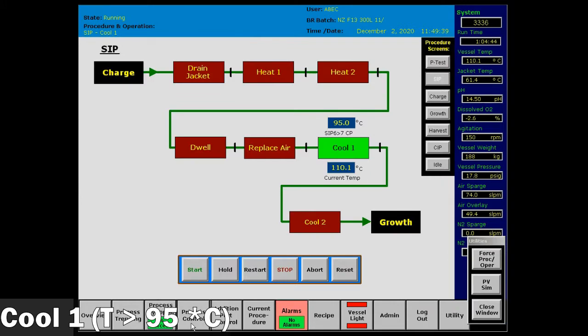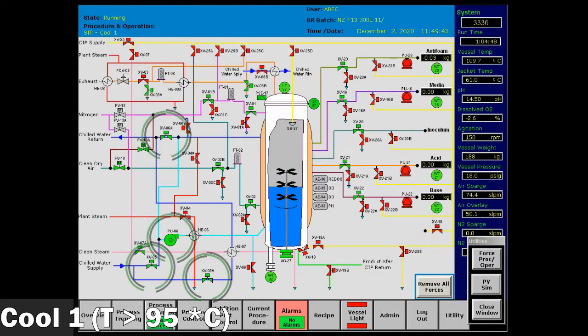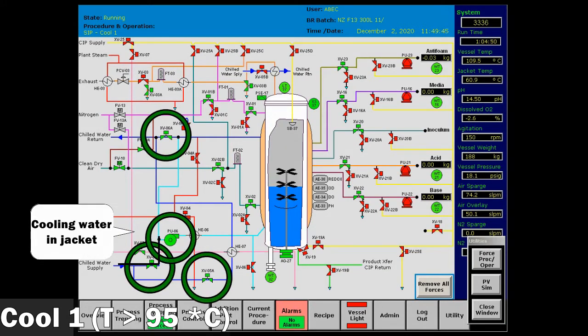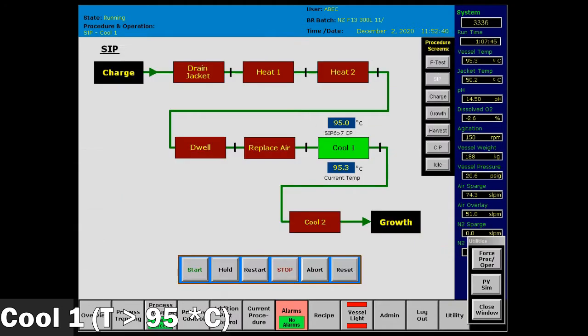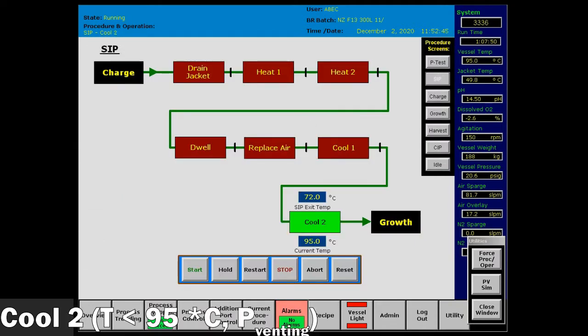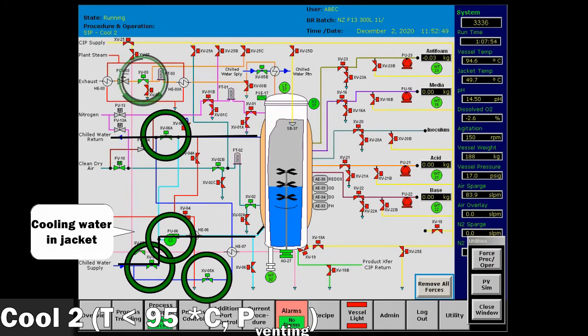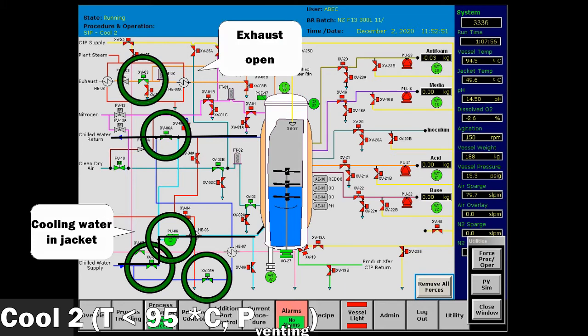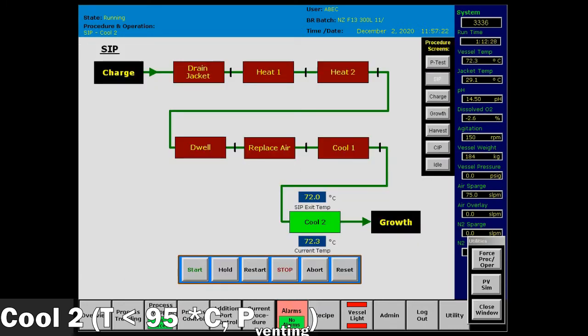The reactor is cooled down to 95 degrees Celsius during Cool 1 by pumping cooling water through the jacket. Pressure is maintained above ambient to avoid the liquid inside the reactor from boiling. Cooling continues to the SIP exit temperature and the exhaust valve opens to vent pressure. SIP cycle concludes and the reactor enters growth mode.